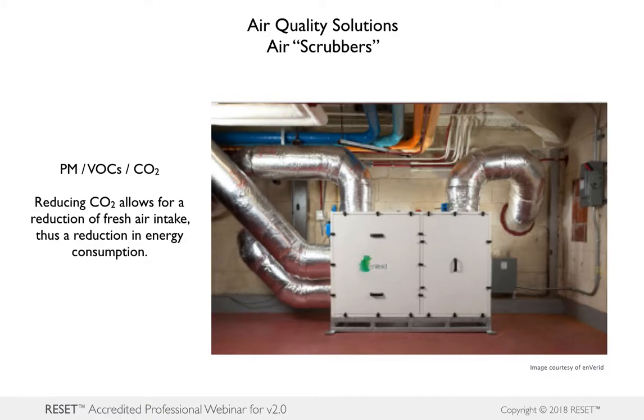And you can actually apply them in either the mechanical rooms or they can be smaller units that are ceiling mounted. But what's important to talk about is that, again, we have some really interesting innovations that are coming on board to actually deal with this idea of how do we reduce and how do we filter, and can we do it with systems that can actually be retrofitted, or can we actually use them in new construction and new design? And in this case, they have units that are accommodating to both scenarios. And it's worth mentioning that, again, once you reduce your CO2, it allows for a subsequent reduction of outdoor air intake and hence reduced energy use.